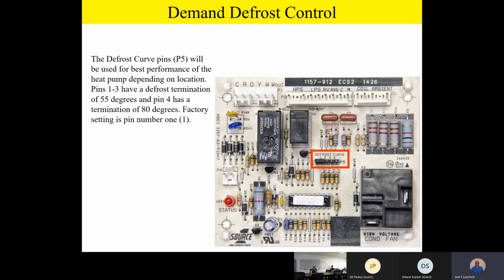And that's the most inefficient way to defrost, because most of the time, if your defrost control is working properly and the sensors are okay and all that stuff, typical defrost is going to be somewhere between about 4 to 7 minutes, but you have a 14-minute backup. So just be aware of that. If you think you're going to move it to pin number 4, and I'm going to get an 80-degree termination, and that's going to give me an absolute defrost every time, it's going to use up more energy, because remember, in defrost mode, team, you're in the heating and cooling mode at the same time, so you're going to be burning up a lot of energy, and you're going to be hitting that 14-minute backup before you reach 80 degrees, I'm going to guess, on your termination points. But that jumper is there for special application.